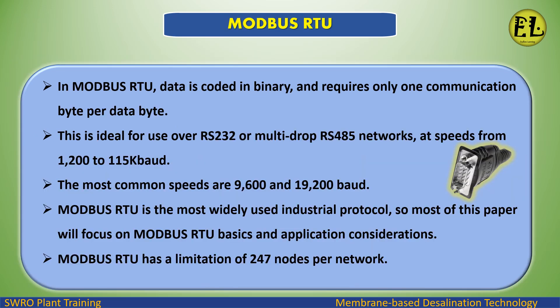Modbus RTU — data is coded in binary and requires only one communication byte per data byte. This is ideal for use over RS-232 or multi-drop RS-485 networks at speeds from 1,200 to 115,200 baud. The most common speeds are 9,600 and 19,200 baud. Modbus RTU is the most widely used industrial protocol. It has a limitation of 247 nodes per network.